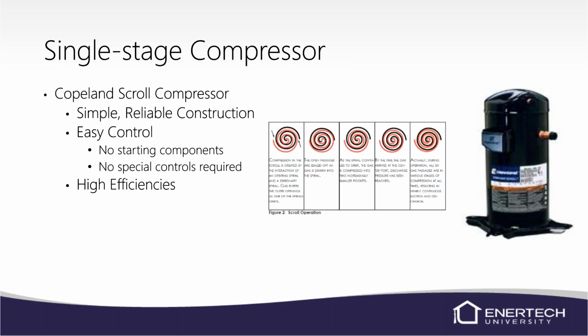You've got two scrolls inside that compressor. You have one stationary and one that's orbiting. So the orbiting kind of moves around and forces that refrigerant into a smaller and smaller space and compresses that refrigerant. Every once in a while, we'll have the stationary scroll damaged in shipping, I've seen, and it'll sound a lot of times like there's gravel in the compressor where those scrolls are knocking together. A lot of times that's due to vibration during shipment, if it starts out on an initial install. That can also happen when the unit's running under adverse conditions, so it could also be caused by the operation of the compressor.